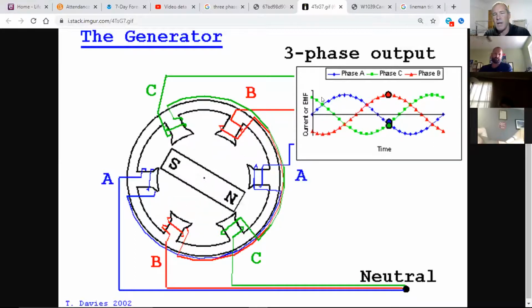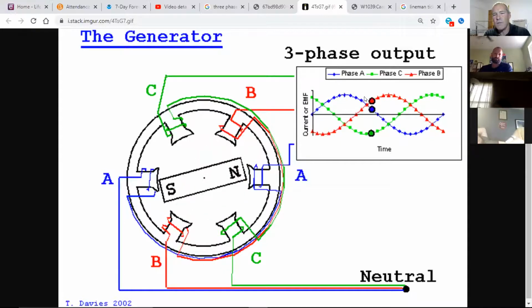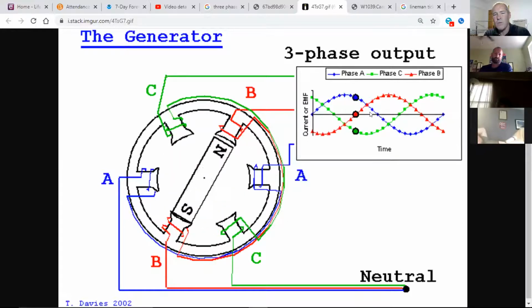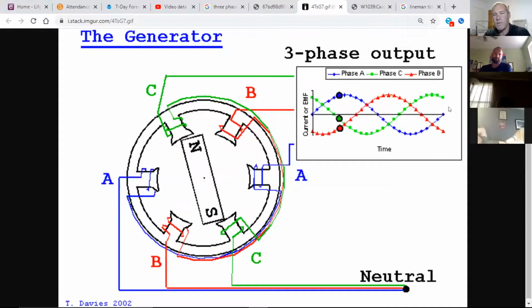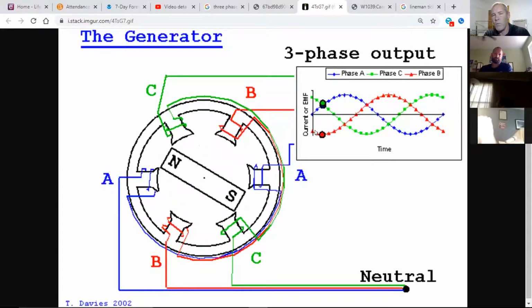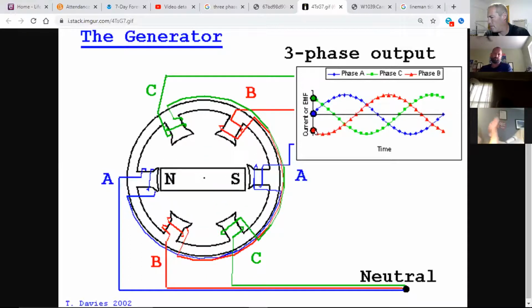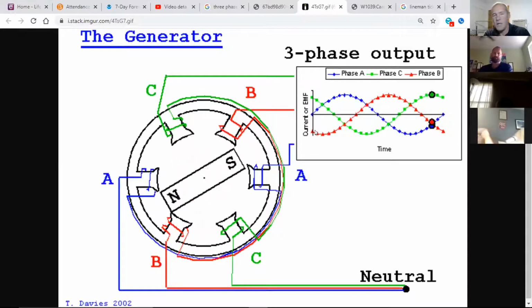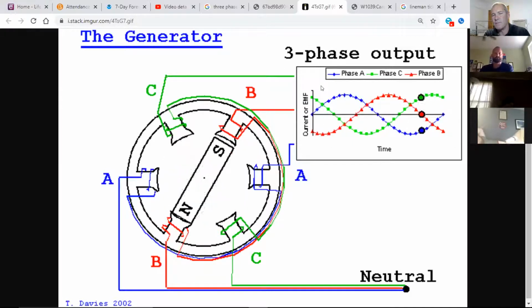That's why when we say in a single phase system, I'll use the blue line for single phase: if that is 7,200 volts I'm generating, 3 times in this sine wave it's at 0. If I'm using all 3 phases at one time, all the time I have 12,470 volts all the time. So you can see how that efficiency is much better in a three-phase system.